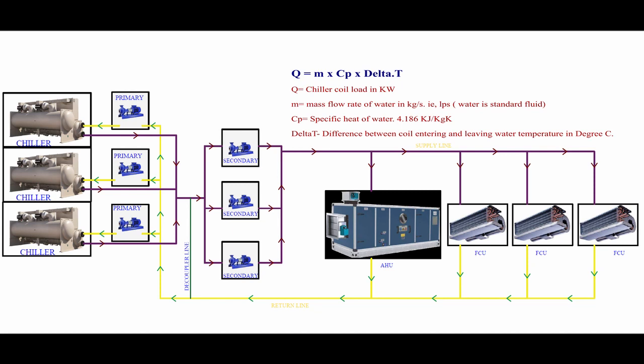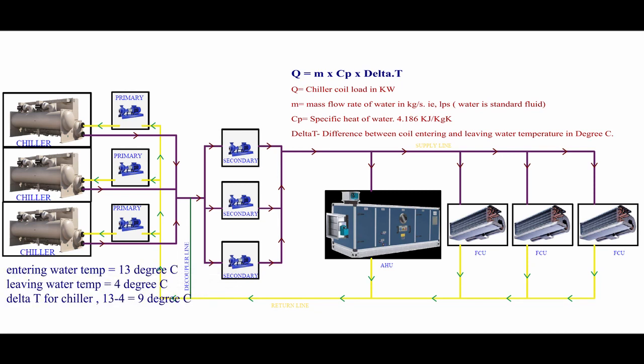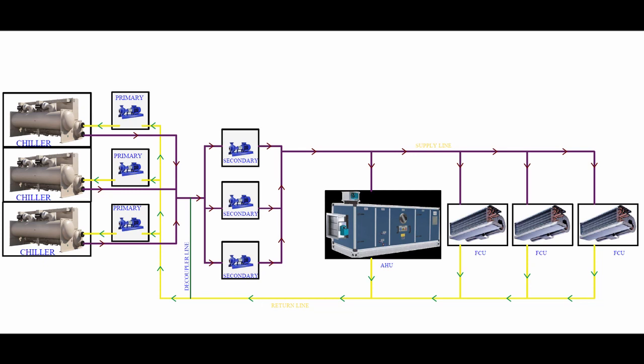Cp is a constant coefficient called the specific heat of water. The value is 4.186 kilojoule per kilogram Kelvin. Delta T is the difference between chiller entering water temperature and chiller leaving water temperature in degree Celsius. Here I am considering entering water temperature as 13°C and leaving water temperature as 4°C, so the delta T of the chiller is 9°C. By the calculation, I will get the mass flow rate of water as around 18.66 kilogram per second.